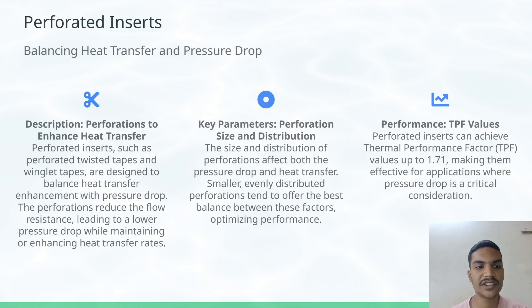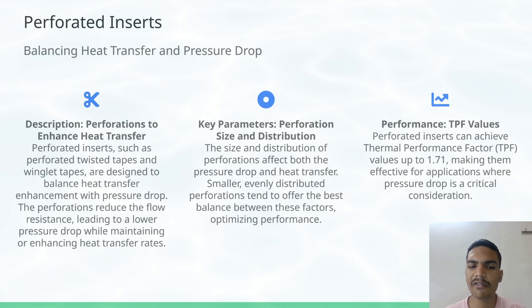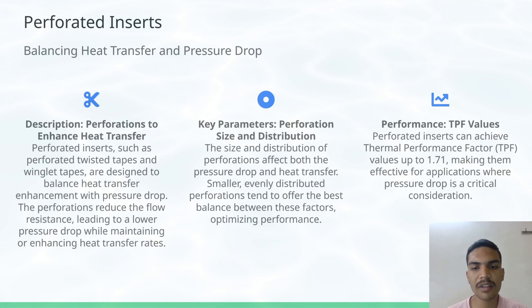Perforated inserts such as perforated twisted tapes, helical perforated tapes, and winglet tapes are designed to balance heat transfer enhancement with pressure drop. The perforations reduce flow resistance, leading to a lower pressure drop while maintaining and enhancing the heat transfer rate. The size and distribution of perforations affect both pressure drop and heat transfer.